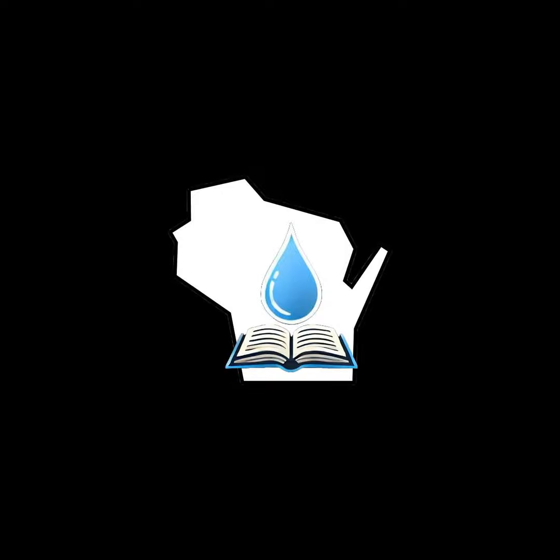Every building also requires at least one main stack. Right below this section in the code, it says each gravity flow sanitary building sewer shall be served by at least one stack, which extends from a building drain to a vent terminal or vent header, not less than 3 inches in diameter. That's your main pressure relief path for the whole system. And remember, the sewer in the code is referencing the sanitary piping outside of the building that's tied on to the building drain. Yes, definitions matter. So let's start to go over wall outlet fixture venting systems.